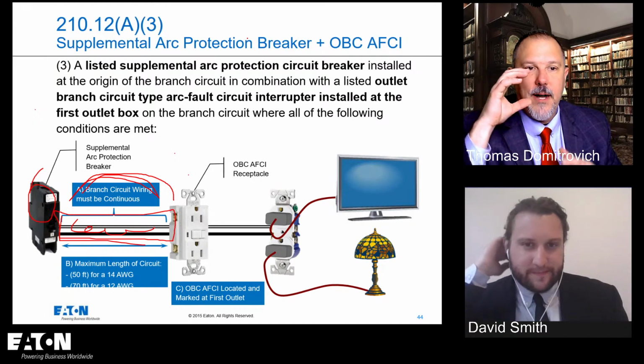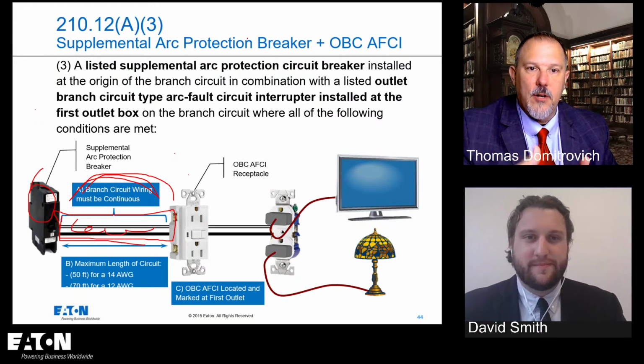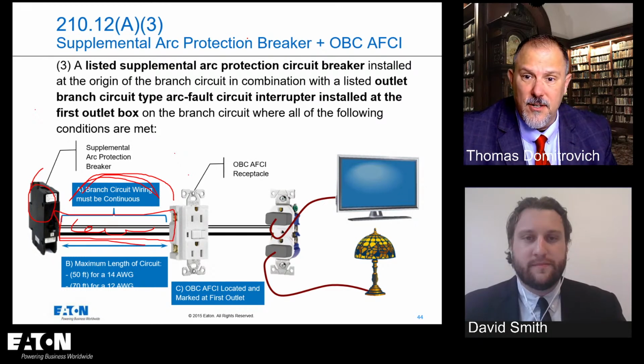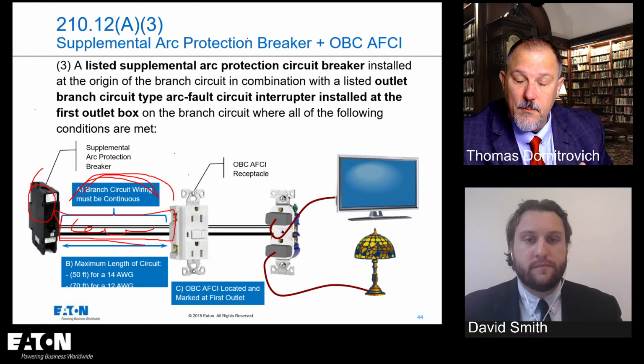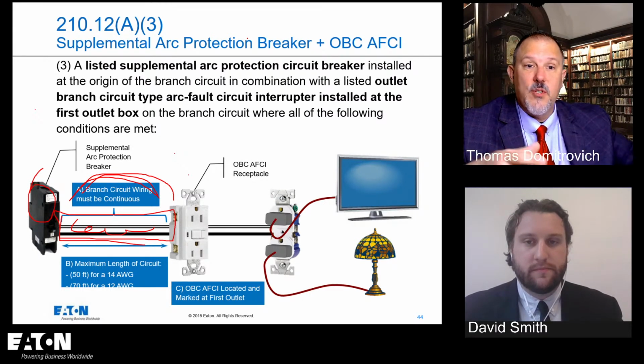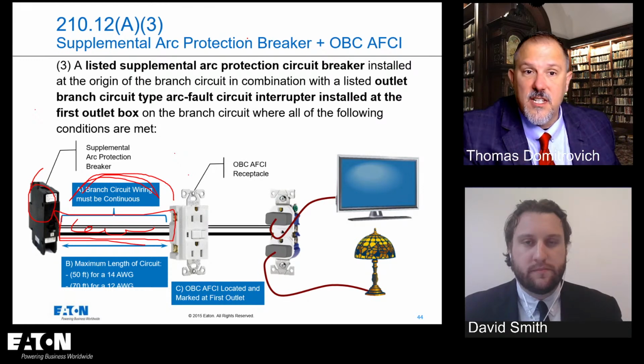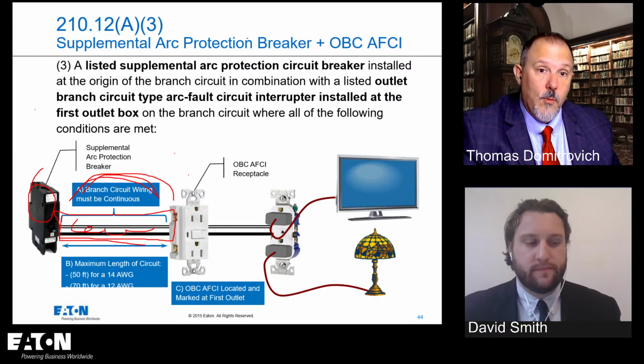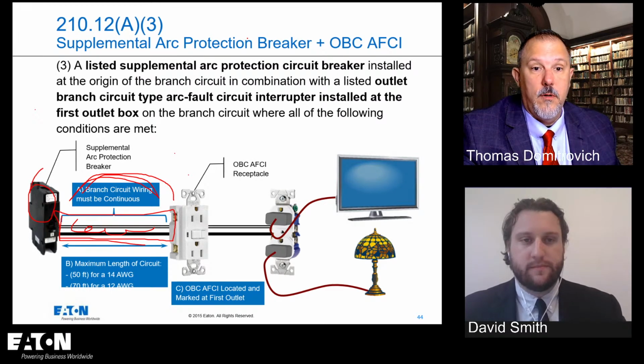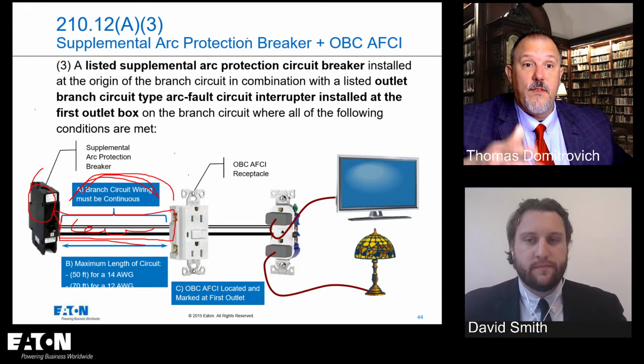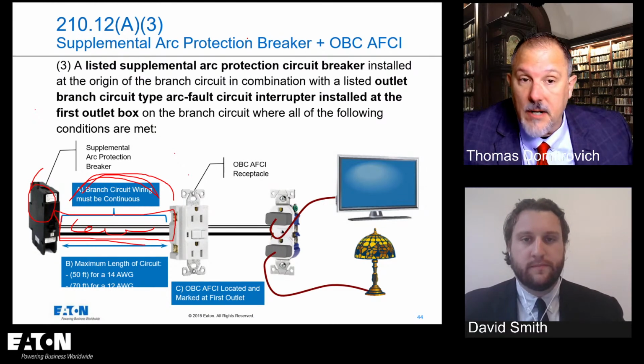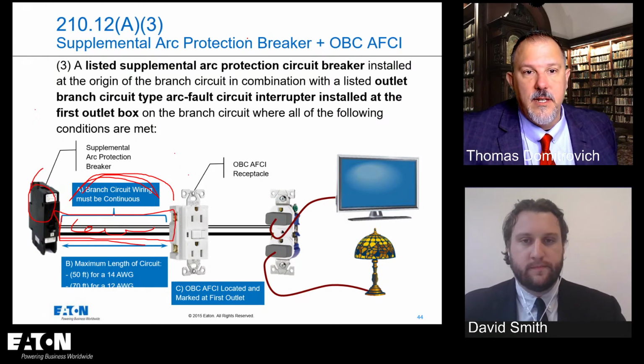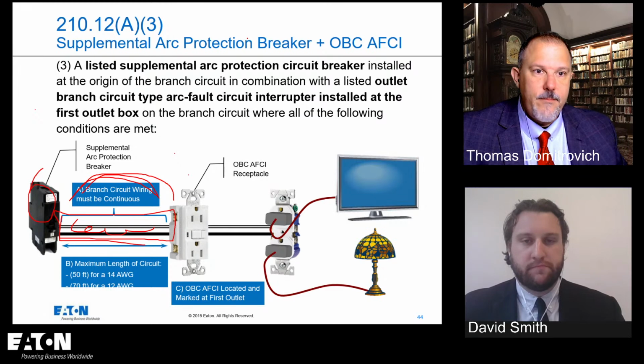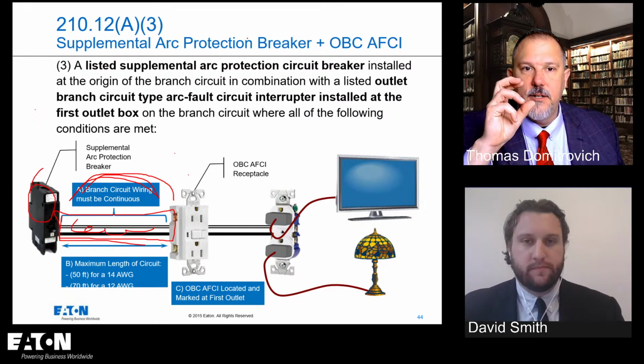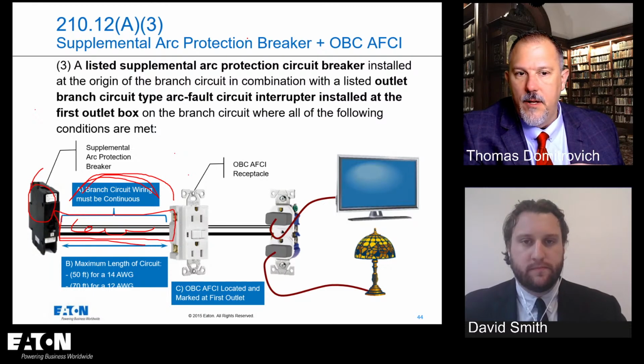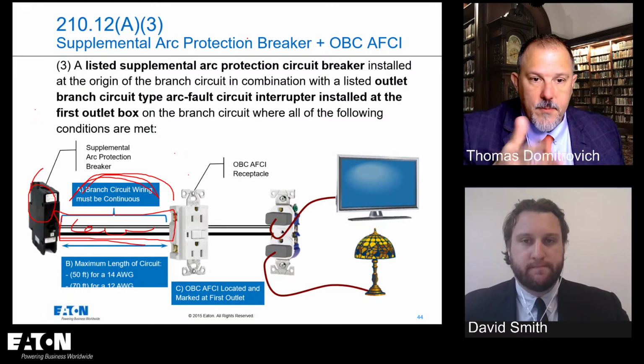Yeah, we're good. So I was just explaining that there is no listed supplemental arc protection circuit breaker because there's no standard for it. This was a debate between these two groups of people. And it's not just the manufacturers, because there are some people that said, hey, we want options. We want to make this possible. And so they said, let's provide one option, which was really the circuit breaker guys who said, we want to bring a supplemental arc protection breaker to the table. And maybe it's something that has just enough electronics in it that can provide that protection for the home run circuit, and it helps make it a viable solution.